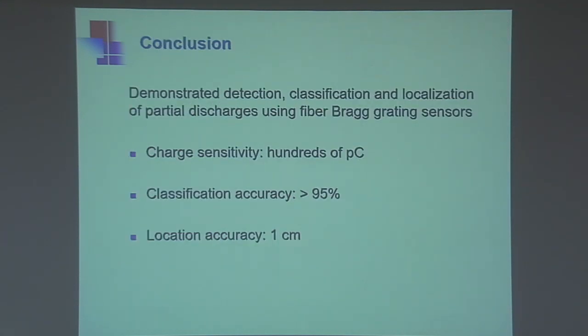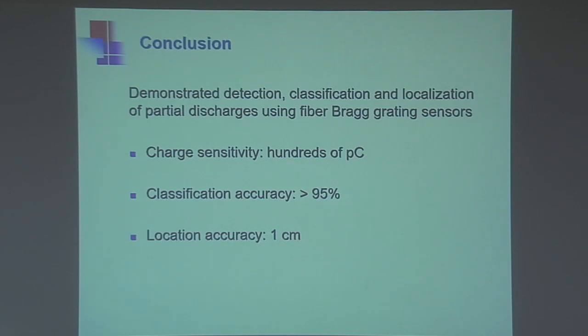To conclude, we have demonstrated detection, classification, and localization of partial discharges in power transformers using fiber Bragg grating-based sensors. We have obtained a charge sensitivity of the order of hundreds of picocoulombs, a classification accuracy of more than 95 percent, and a location accuracy of the order of a centimeter. In short, we have proved that fiber Bragg gratings are tangible solutions for condition monitoring of power transformers.